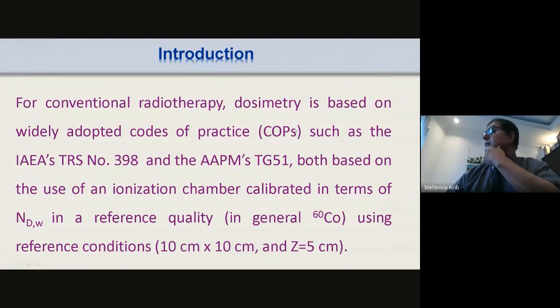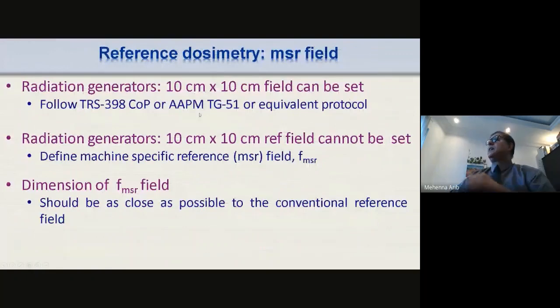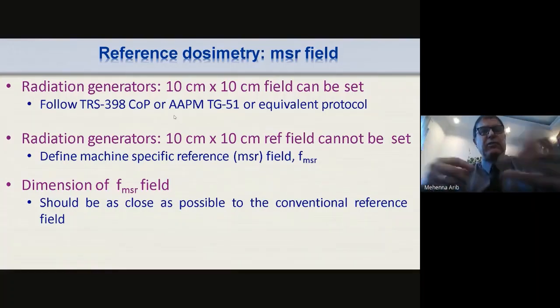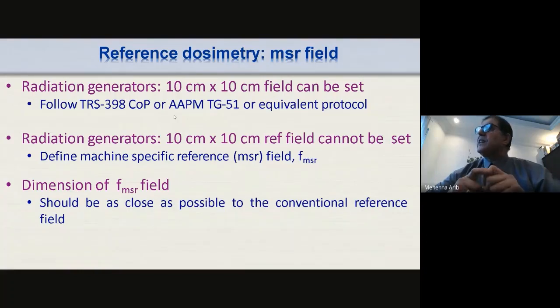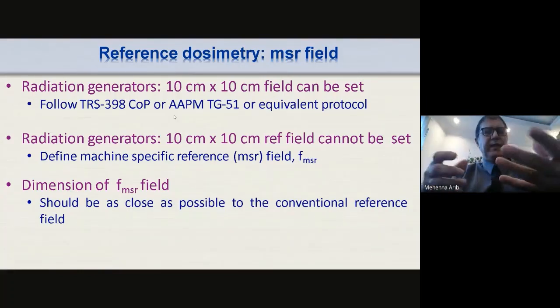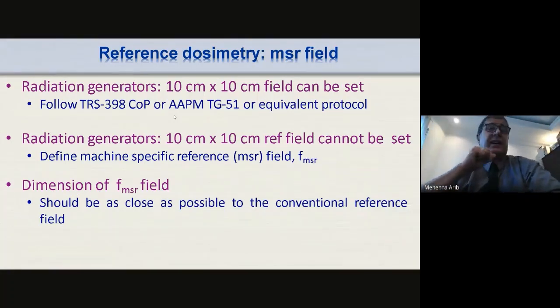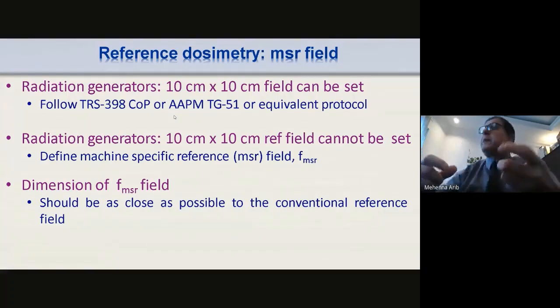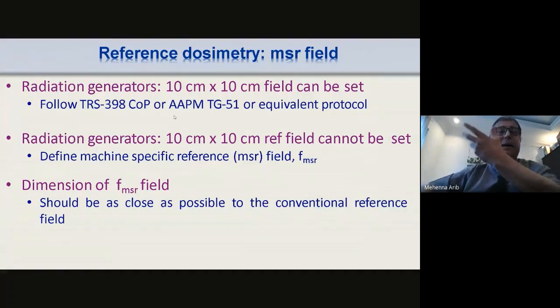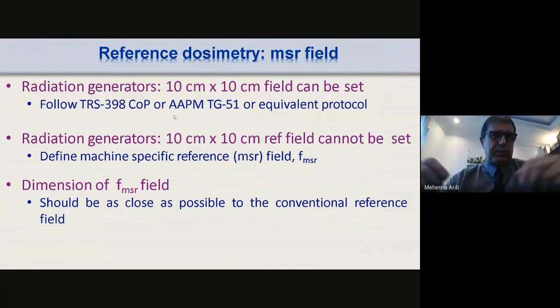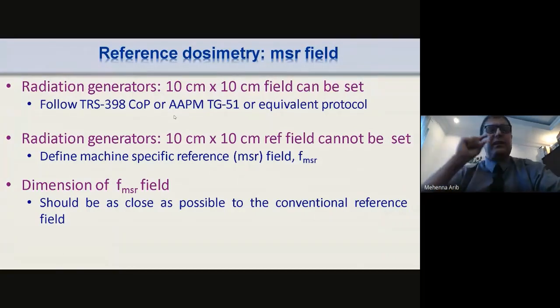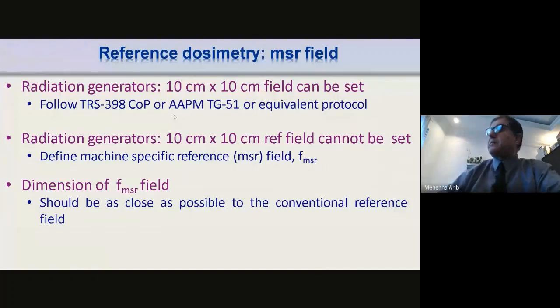When it comes to reference dosimetry, previously we had machines able to get big field sizes, more than 6 by 6. But now we have plenty of new and modern machines that can get what we call machine-specific reference fields, which is not necessarily 10 by 10. So we have radiation generators having a field size of 10 by 10, and you have radiation generators which cannot achieve 10 by 10, like Cyberknife and Tomotherapy. We have just small fields. In that case, we define the machine-specific reference field, which is specific to that machine.